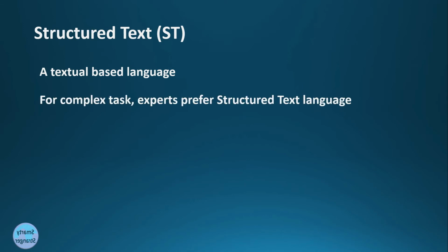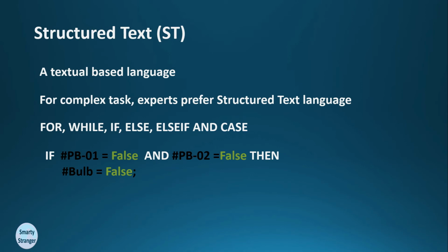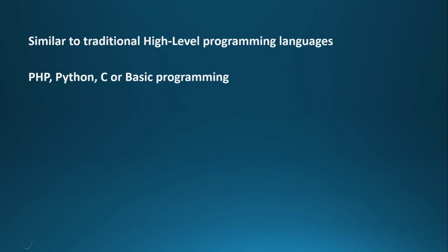Structured Text, ST. Structured Text, a textual-based language. For complex tasks, experts prefer structured text language. You must write out each line of code and it uses functions such as for, while, if, else, else if and case. Since structured text is similar to traditional high-level programming languages, it can be fairly easy for many people who may not have a background in PLC programming but have experience in traditional coding to learn and develop PLC projects. If you know the concept of high-level programming languages like PHP, Python, and C, then structured text is a good idea for you. Best suited for mathematical or complex programs.